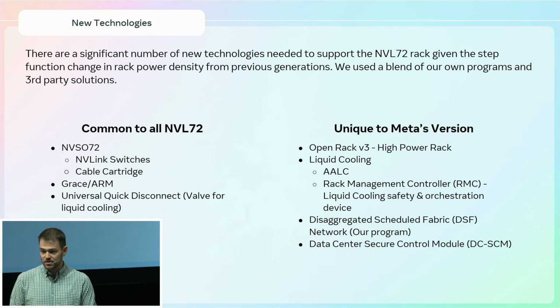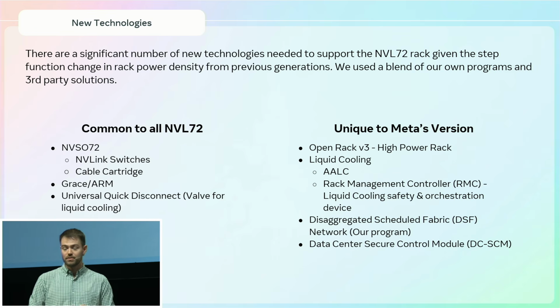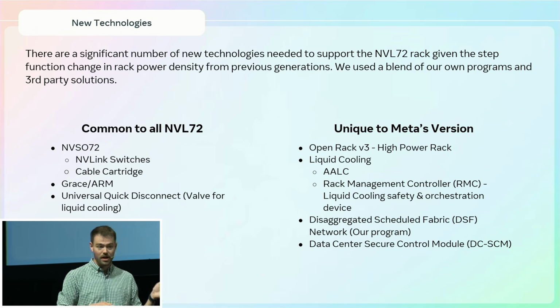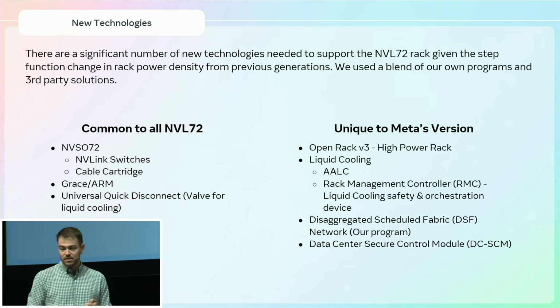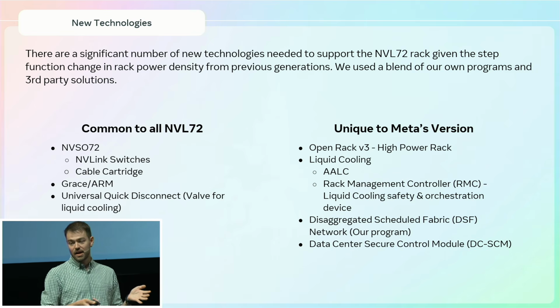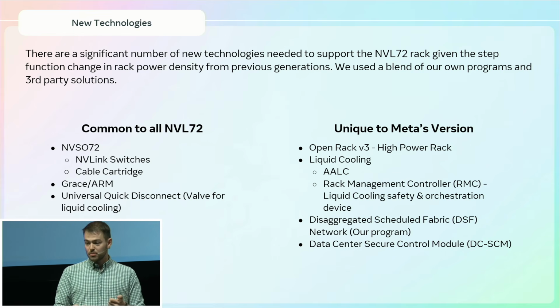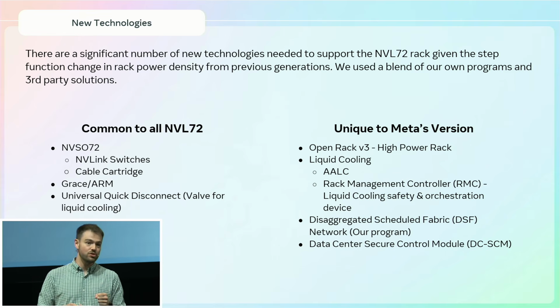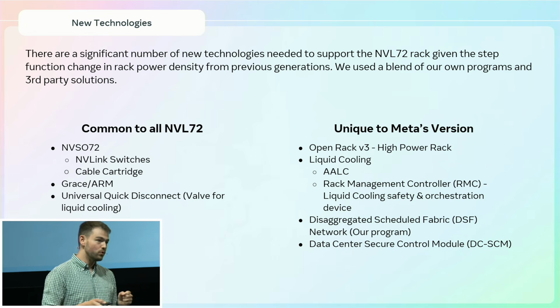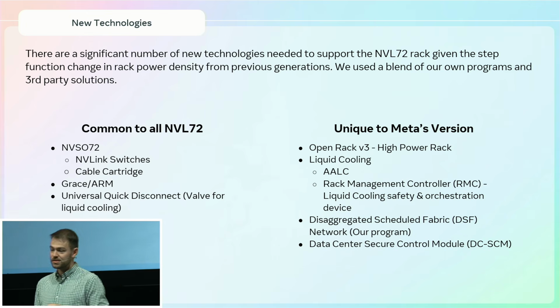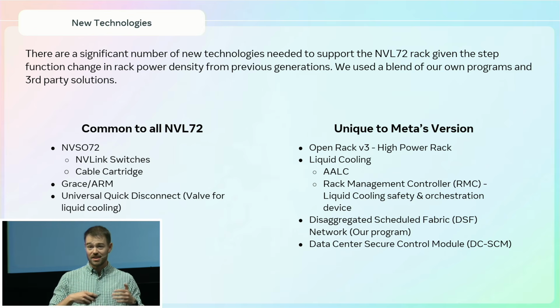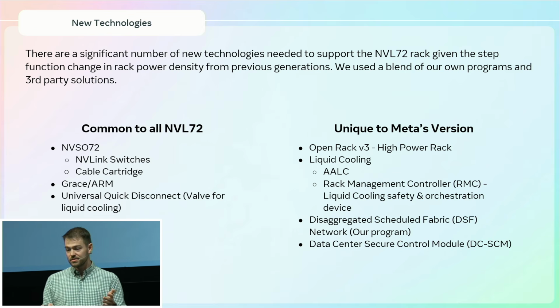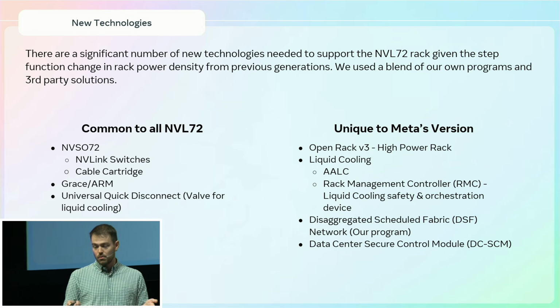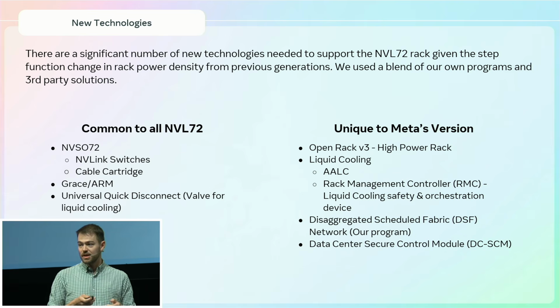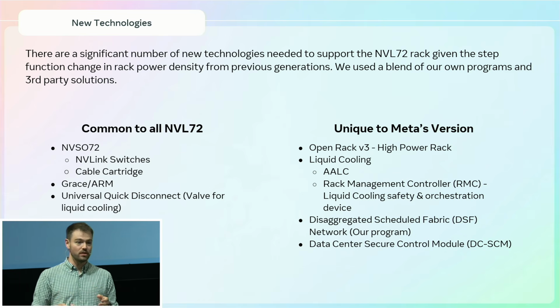Unique to Meta, there were a few things we have, like the high power version of our Open Rack V3 - essentially higher powered power supplies and BBUs. We had liquid cooling, so the air-assisted liquid cooling needed to support those racks in traditional data centers. The rack management controller is basically a safety and orchestration device that helps enable and disable cooling and also does monitoring for leaks in the racks. We have our network topology, the disaggregated scheduled fabric, which allows us to connect multiple of these pods together to make larger clusters. And then we have our data center secure control module, which Matt will be talking about in more detail, but basically does things like the out-of-band management within the host.